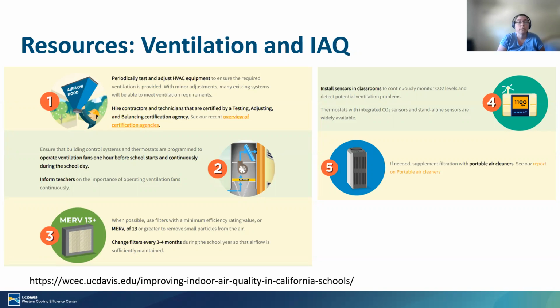Use filters MERV 13 or better. And I'm going to talk about what that means, and change filters a couple times a year, every 3 to 4 months, to make sure airflow is maintained. Install carbon dioxide sensors into classrooms to monitor CO2 levels. I'll talk about that more as well. And then, if needed, supplement filtration with portable air cleaners. I have a link here on our website that has a report on portable air cleaners and things you should look for. And I talk about that a little bit more as well.